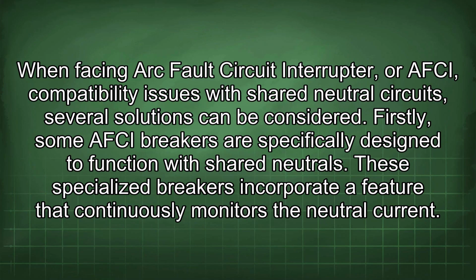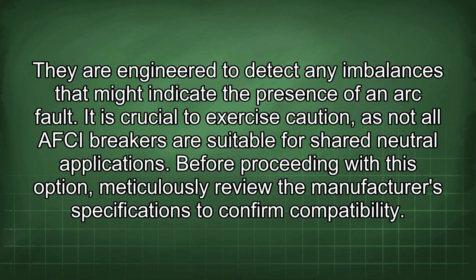When facing arc fault circuit interrupter, or AFCI, compatibility issues with shared neutral circuits, several solutions can be considered. Firstly, some AFCI breakers are specifically designed to function with shared neutrals. These specialized breakers incorporate a feature that continuously monitors the neutral current. They are engineered to detect any imbalances that might indicate the presence of an arc fault. It is crucial to exercise caution, as not all AFCI breakers are suitable for shared neutral applications. Before proceeding with this option, meticulously review the manufacturer's specifications to confirm compatibility.